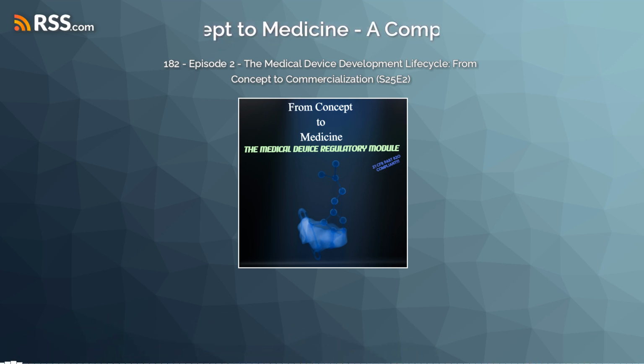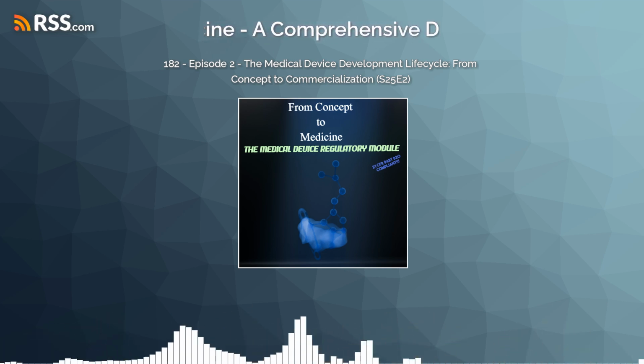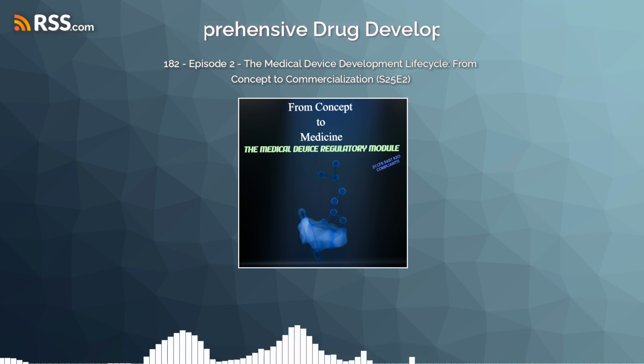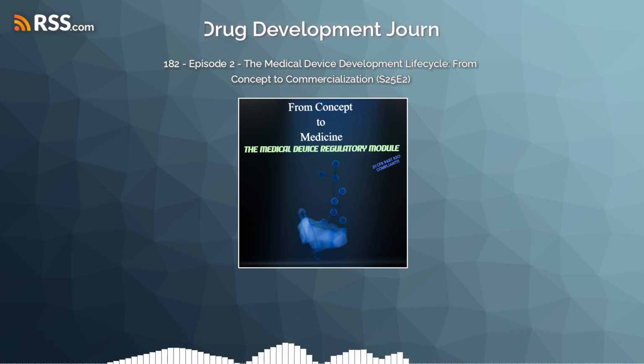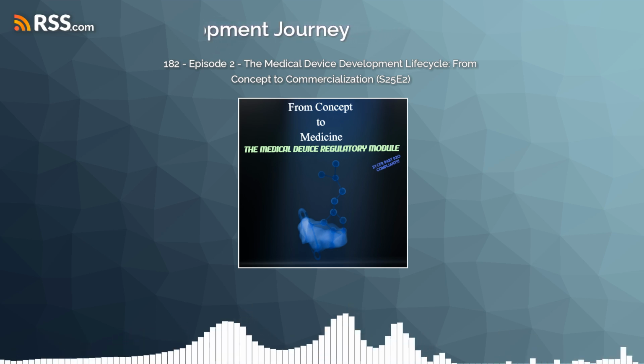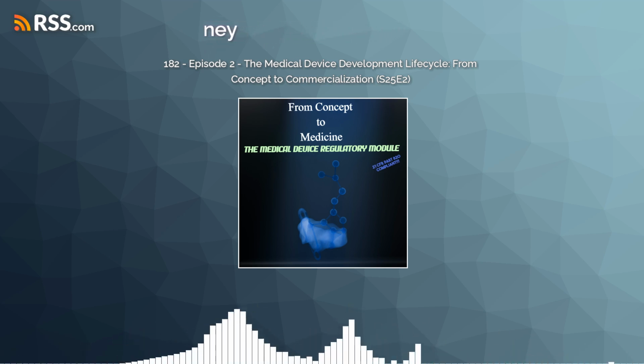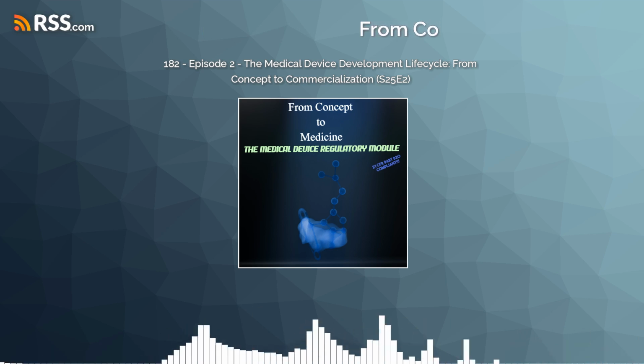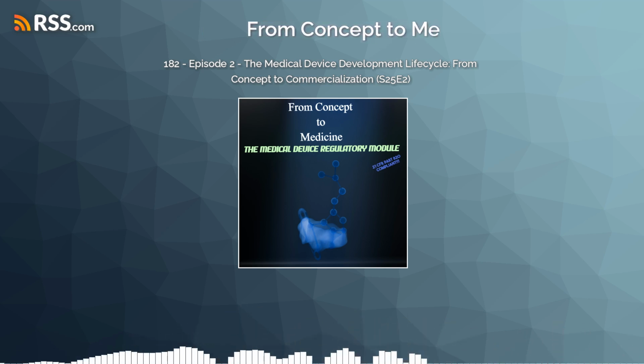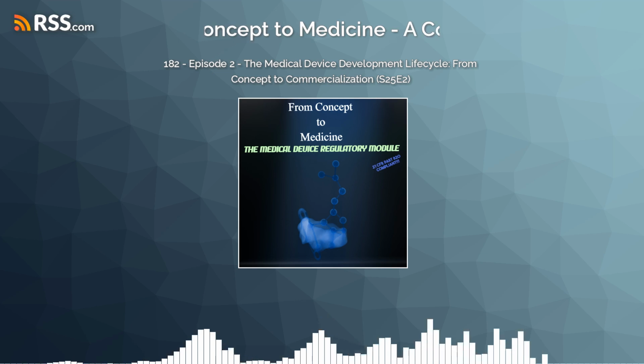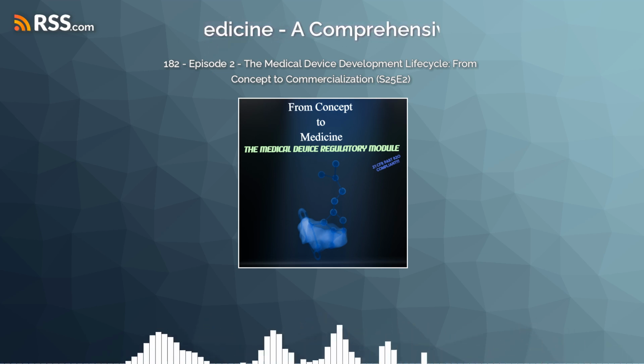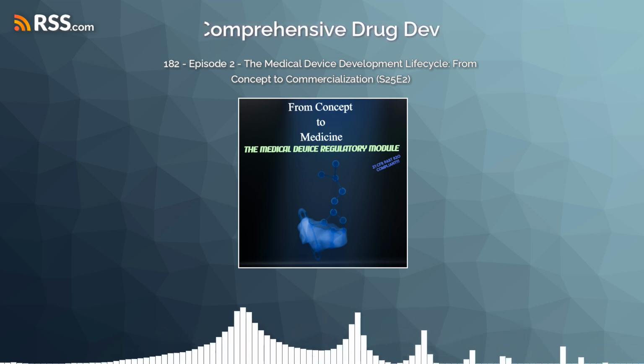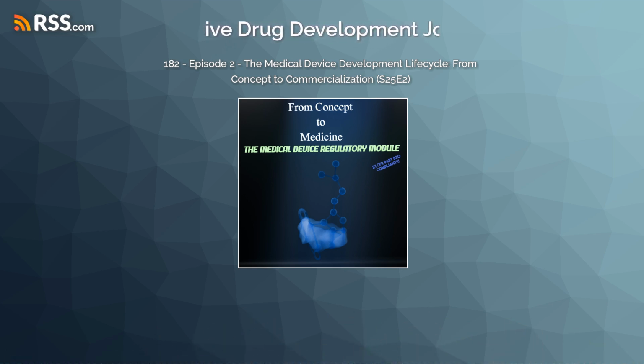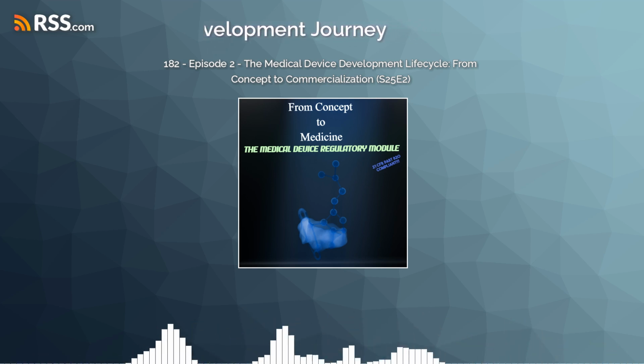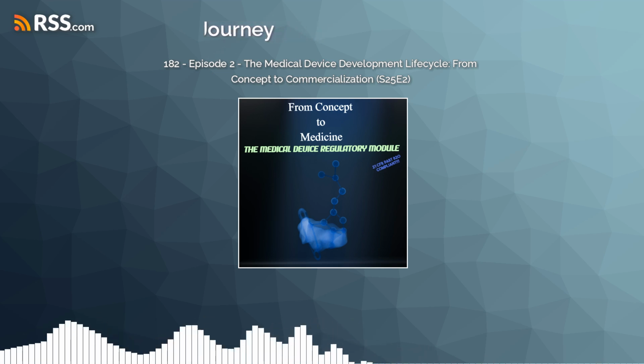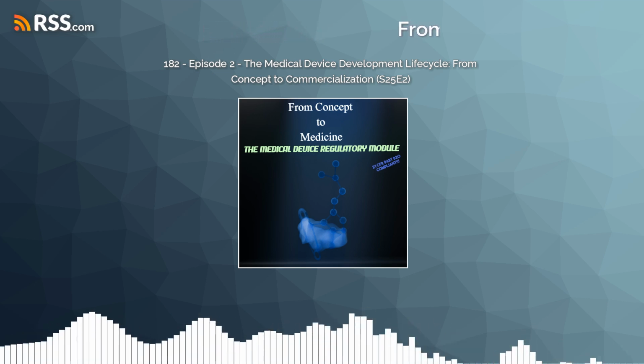Okay. And you mentioned equipment. Yes. A huge part of GLP is equipment qualification. You can't trust the test results if you can't trust the equipment doing the testing. Makes sense. So it's usually a 4-step process. DQ, design qualification. Is this the right tool for the job? IQ, installation qualification. Is it installed correctly? OQ, operational qualification. Does it work properly across its range? And PQ, performance qualification. Does it perform consistently in the real environment? DQ, IQ, OQ, PQ. Wow. That's thorough just for the testing gear.